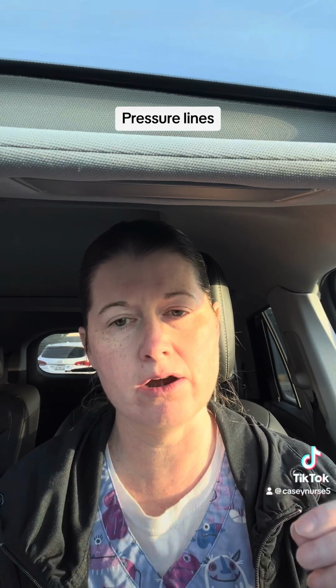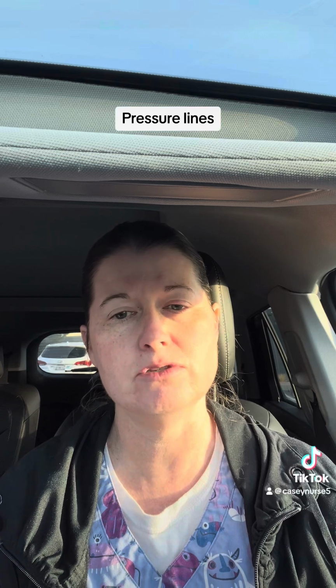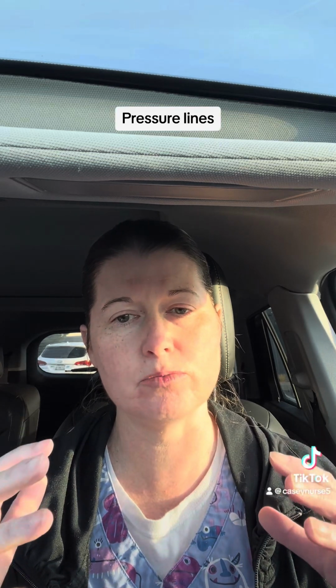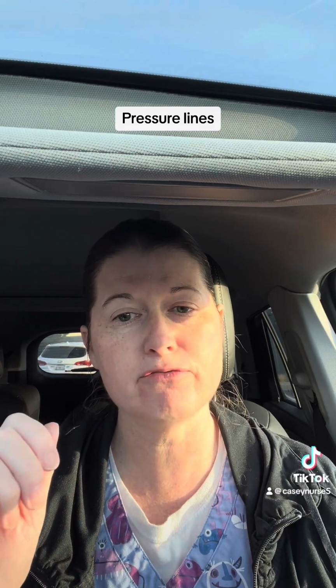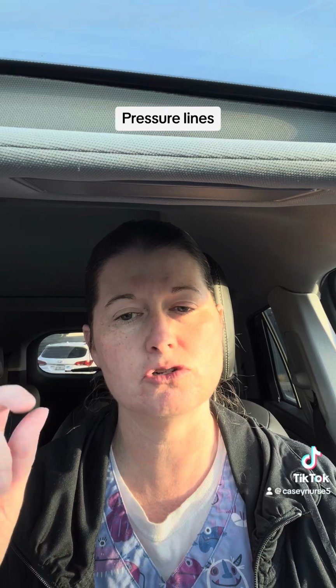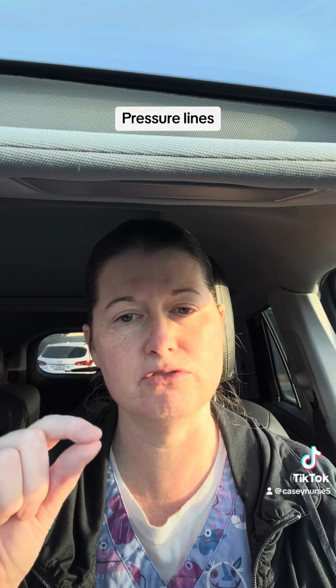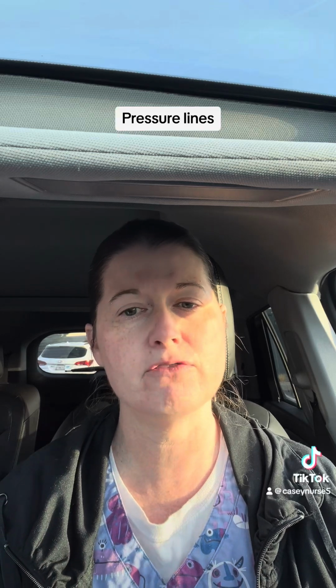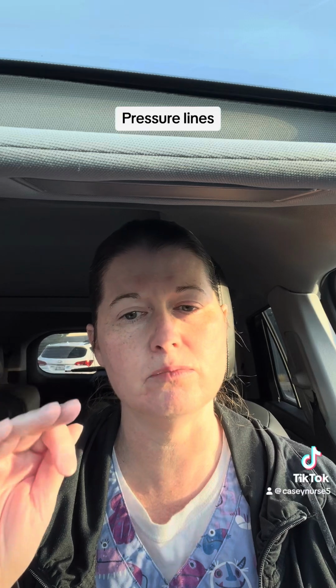You open the transducer to air, and you tell it ignore all of this atmospheric pressure pushing on us around and only measure the pressure inside the patient. So you have to turn the stopcock off to the patient. So you're going to turn it off to the hard tubing. You're going to feel which side has the hard tubing, turn it off to that, take the cap off, hit 0 on your monitor, and then once it says 0, then you can put your cap back on and turn your stopcock back off to the little port, and you should be good to go with your blood pressure.